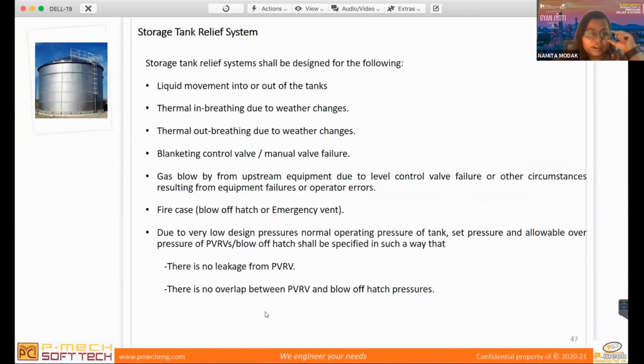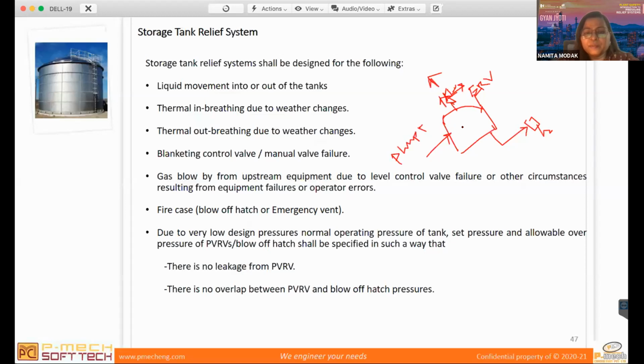Okay, so now particularly talking about the storage tank. So normally in a storage tank, it can be a water tank, or it can be sometimes dome shaped, sometimes a cone type floating roof, based on whatever the service you are giving. So here you will see we provide the breather valves, through which in-breathing and out-breathing can be performed through the same valve, and then we give the ERVs, emergency relief valves. So basically, these breather valves are sized based on the pump in and pump out flow rate. So the out-breathing flow rate is considered by pump in plus any expansion because of thermal.